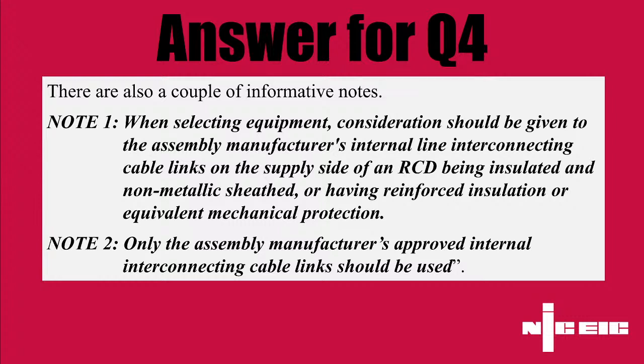So if we do it on the generic that we've got a very low ZS because we've got a very high current rating protective device, but we might be a little bit away from our origin, so our incoming ZE is already higher than the rating of the protective device. We have got a solution, haven't we, Dan? I'm just going to find the section, because this does happen, especially on larger plants, where because of the rating of the incoming device, you've got a very high rated overcurrent protective device, which effectively means you've got a very low ZS to achieve, and there will be instances where you just can't achieve that ZS. So 7671 then does draw you to, and I think it's 419. You'll tell me if I'm right? Yes, I was going to 415, but then you said 419.